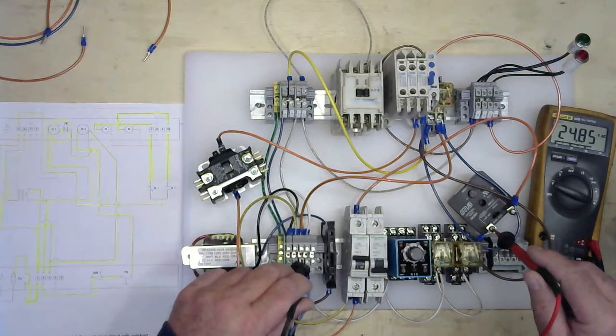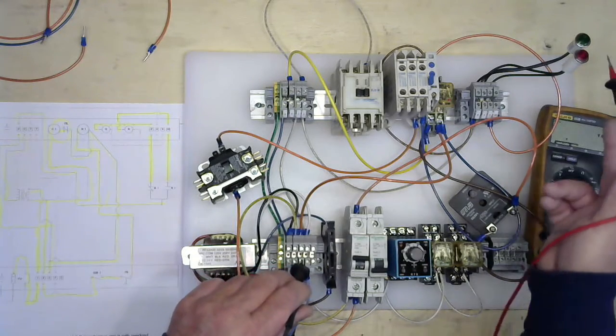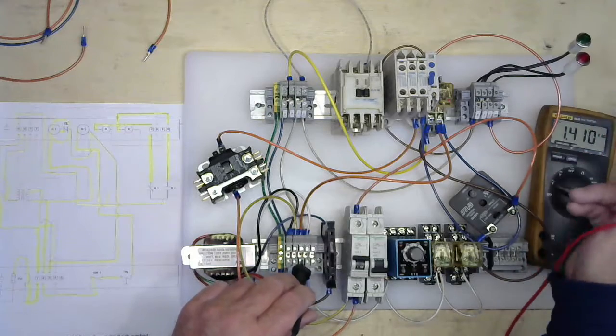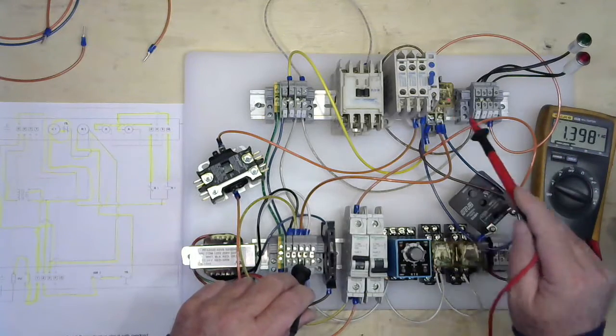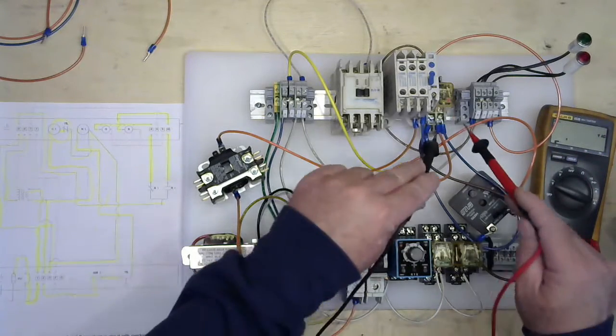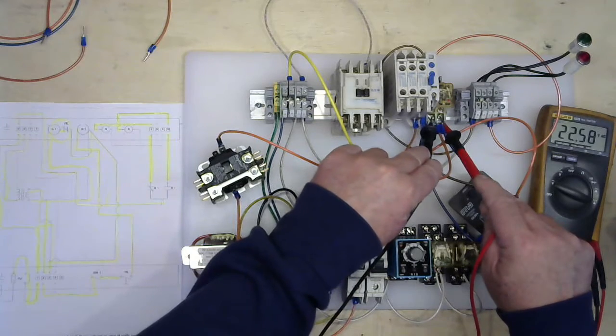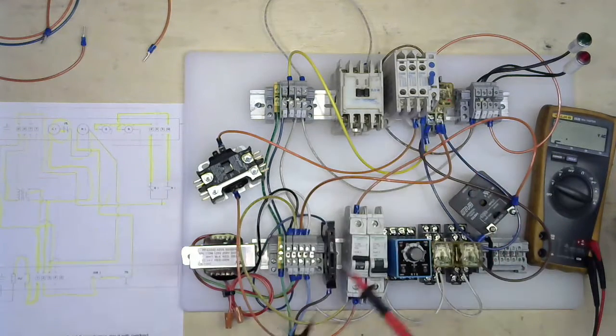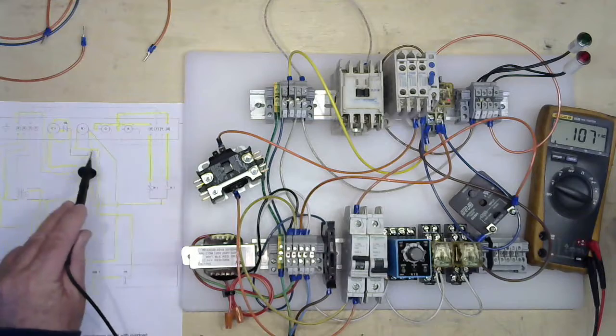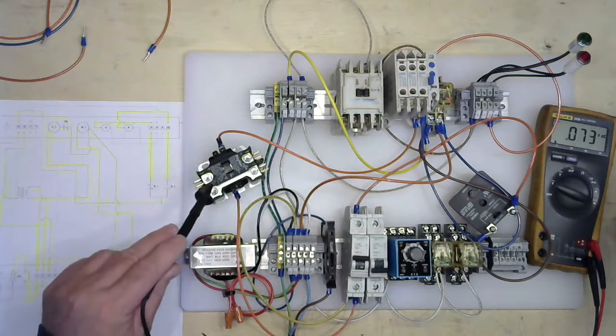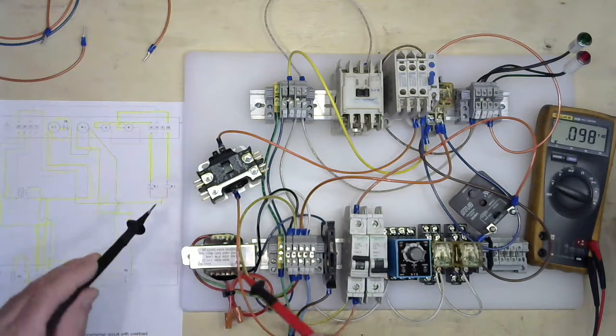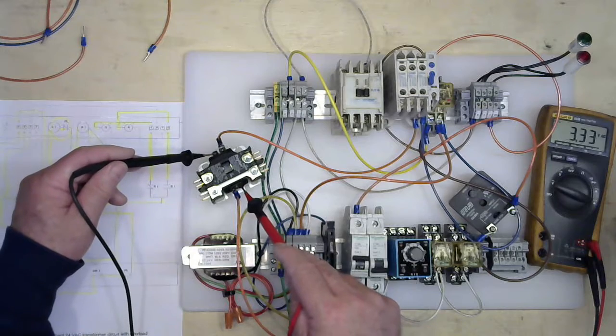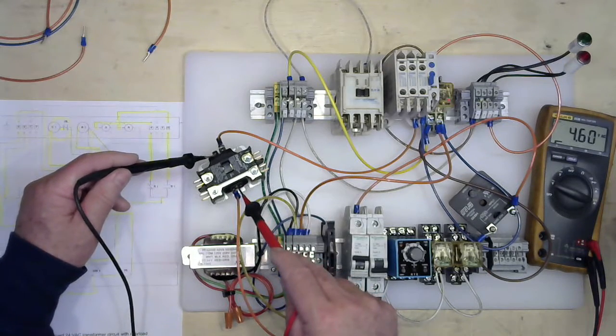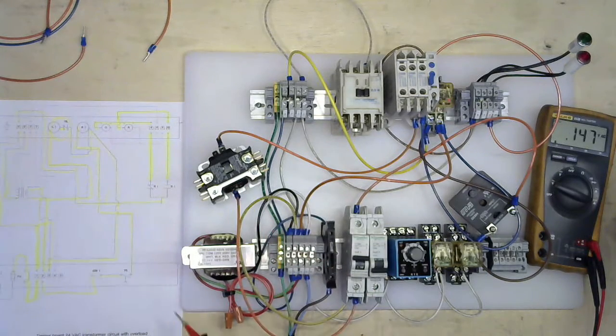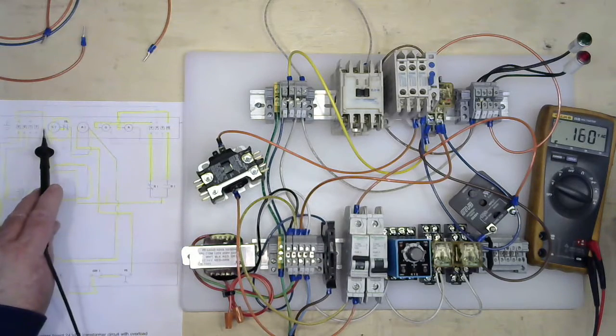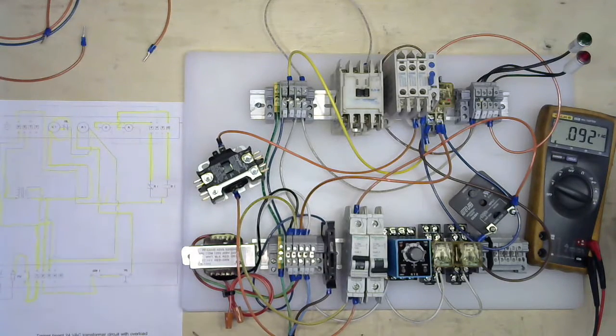Now my time delay just timed out. My lights have changed status, and my coil here is now energized. If I check across my meter, my coil's energized. My contacts here, coil's energized, contacts here, and my coil is still energized because my contactor's pulled in, because as soon as I apply power to my transformer, my coil pulls in.